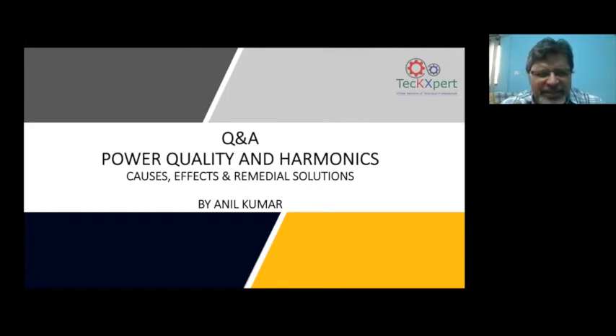So I would rather say in this particular case, or if you are proposing such solutions, yes, cost is an important thing, but to economize the cost, do good system engineering and decide whether a line reactor is the better option, or a common active filter, or a common passive filter. You can put these VFDs together. For example, let's say you have 10 VFDs of 50 kilowatt. Then you put together 500 kilowatt as total and put one passive filter for all the 500. That way also you can reduce the cost. That means you have to do that engineering and optimize the cost. That is how we can bring down the cost, I would say.